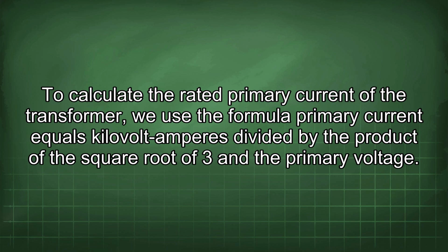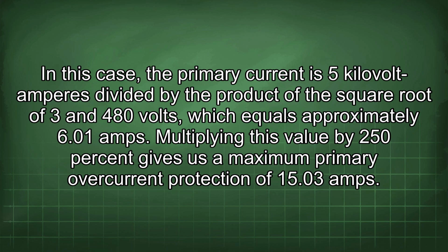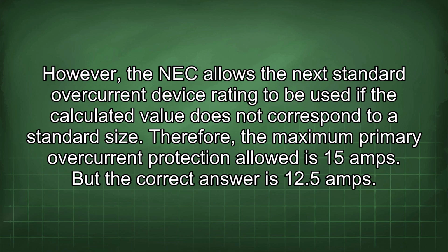To calculate the rated primary current of the transformer, we use the formula: primary current equals kilovolt amperes divided by the product of the square root of 3 and the primary voltage. In this case, the primary current is 5 kilovolt amperes divided by the product of the square root of 3 and 480 volts, which equals approximately 6.01 amps. Multiplying this value by 250% gives us a maximum primary overcurrent protection of 15.03 amps. However, the NEC allows the next standard overcurrent device rating to be used if the calculated value does not correspond to a standard size. Therefore, the maximum primary overcurrent protection allowed is 15 amps, but the correct answer is 12.5 amps.